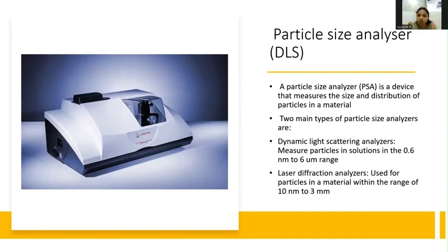If the concentration of the solution is too high, you may not get a good Gaussian curve. Actually, the result of this DLS will be a Gaussian curve, showing the distribution of the particle size. If you have a very saturated solution, the Gaussian curve may not be very good, and you will get erratic results because your samples are getting agglomerated. So yeah, an ideal concentration should be used for doing this analysis.